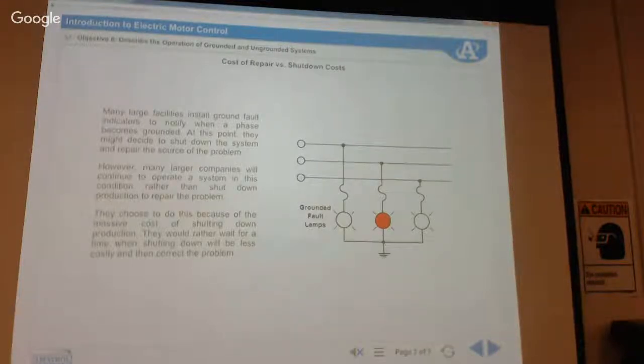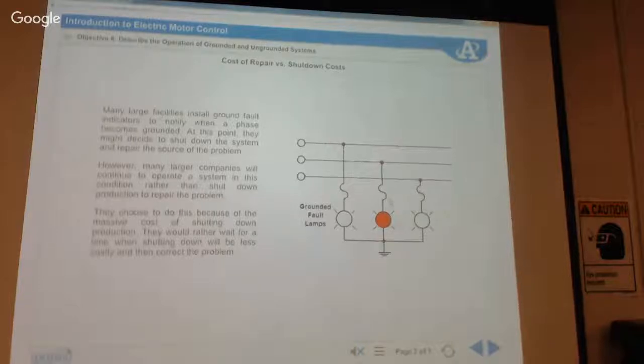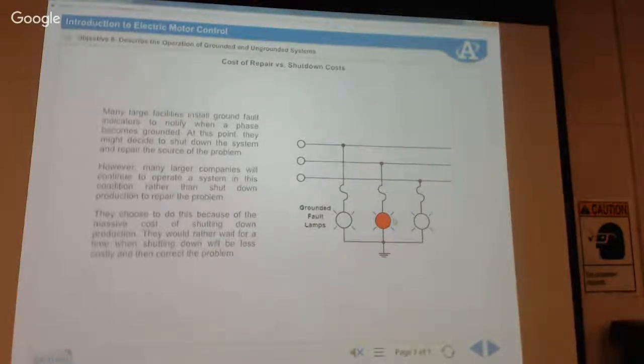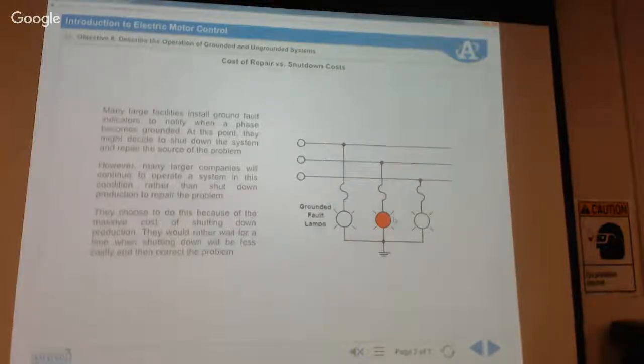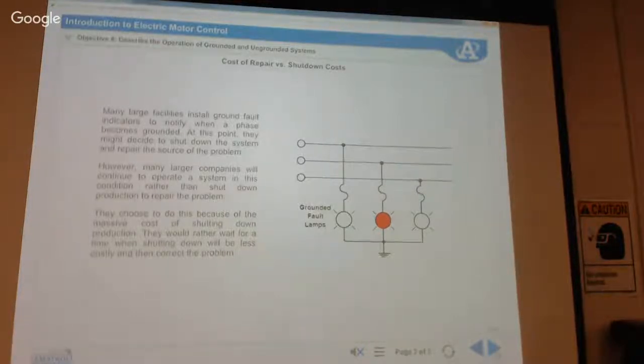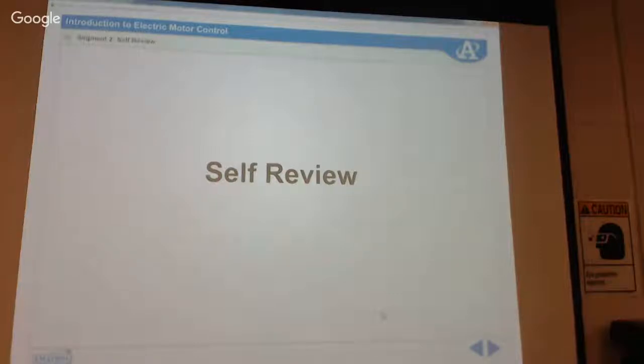This talks about a large facility installing fault indicators to let them know when a phase is grounded. And those are simply indicator lights or indicator devices. Most of this would be located in a room nobody goes in, so a light's not going to do you any good. It needs to be an email device, digital device, or a horn or something. Even on your SCADA system control room, they'll show up. You need some kind of signal to notify somebody. HMI or SCADA system. Orange good.